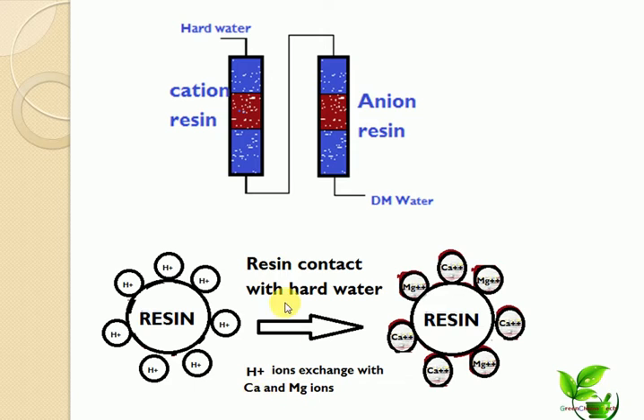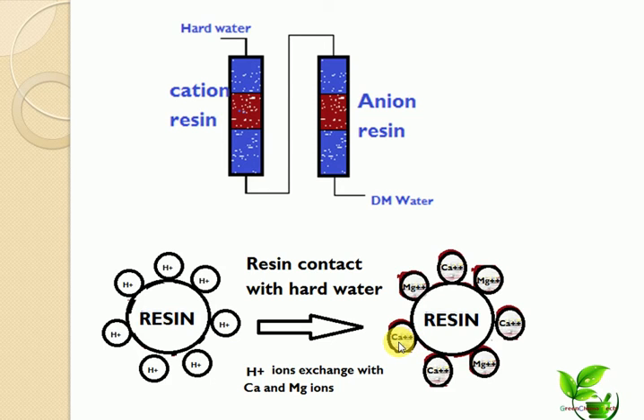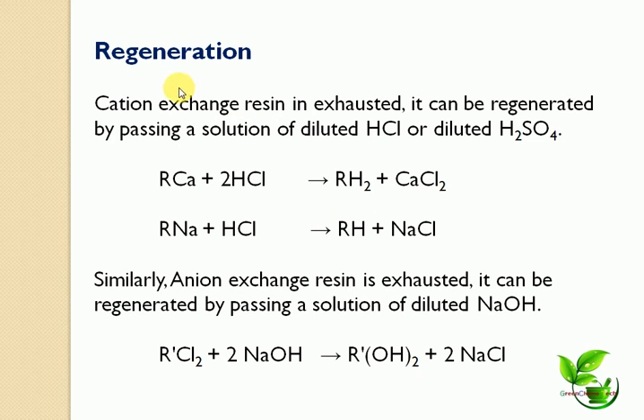The cationic resin exchanges H⁺ ions with Ca²⁺ or Mg²⁺ ions. Once all H⁺ ions have been exchanged, no free functional groups remain, and the microporous structure becomes blocked. At this point, the resin is exhausted and can no longer remove hardness-producing ions from large quantities of water. Regeneration is then required.